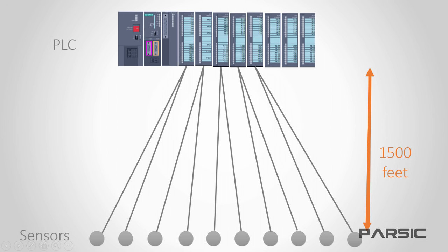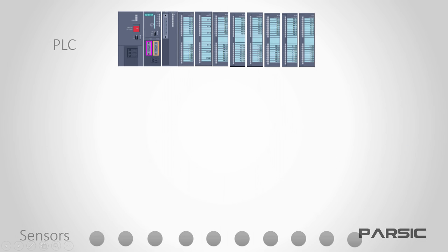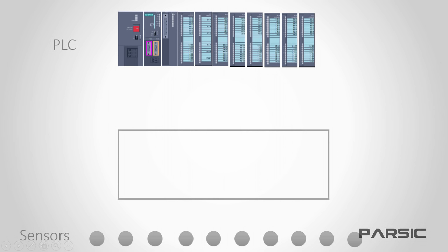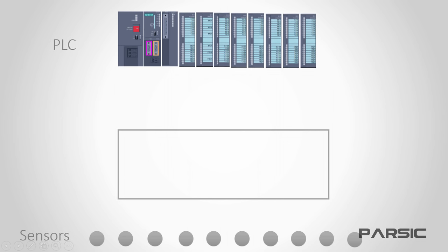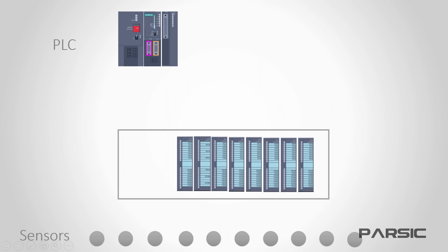Now, let's see how the wiring will change when we utilize a Profibus DP network. At the moment, our I.O. modules are situated right next to the CPU. To use Profibus DP, we can put an enclosure near the sensors in the field area and then move the I.O. modules into it. Then we can connect the sensors to the I.O. modules.